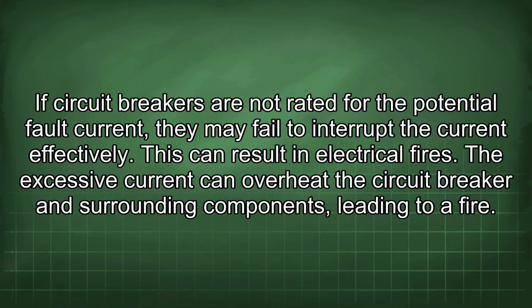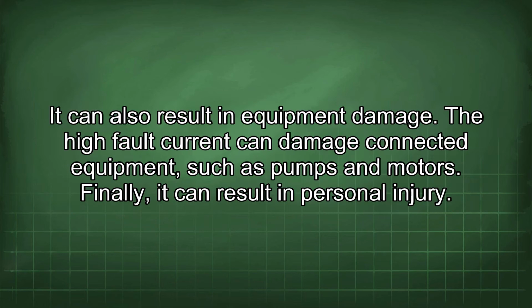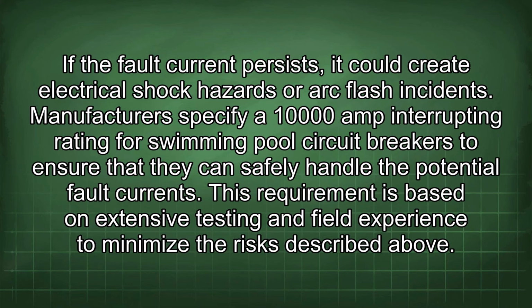If circuit breakers are not rated for the potential fault current, they may fail to interrupt the current effectively. This can result in electrical fires. The excessive current can overheat the circuit breaker and surrounding components, leading to a fire. It can also result in equipment damage. The high fault current can damage connected equipment, such as pumps and motors. Finally, it can result in personal injury. If the fault current persists, it could create electrical shock hazards or arc flash incidents.